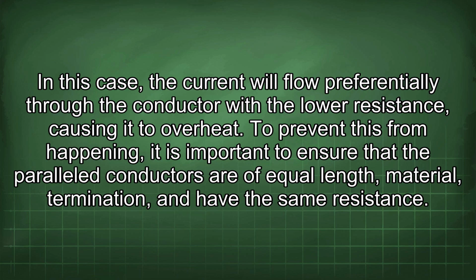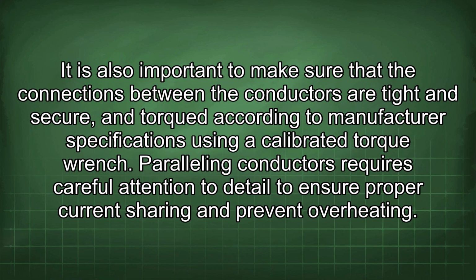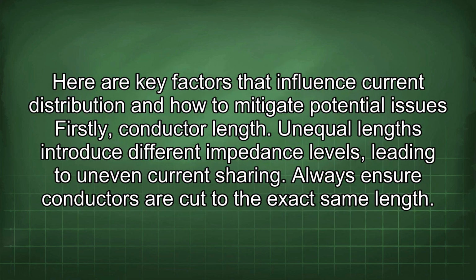To prevent this from happening, it is important to ensure that the paralleled conductors are of equal length, material, and termination, and have the same resistance. It is also important to make sure that the connections between the conductors are tight and secure, and torqued according to manufacturer specifications using a calibrated torque wrench. Paralleling conductors requires careful attention to detail to ensure proper current sharing and prevent overheating. Here are key factors that influence current distribution and how to mitigate potential issues.